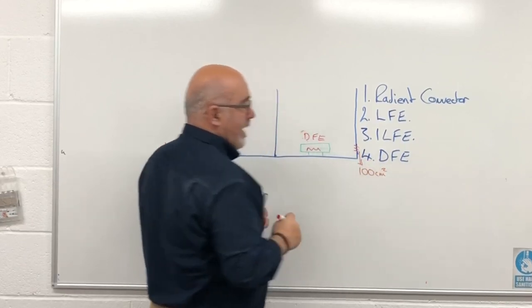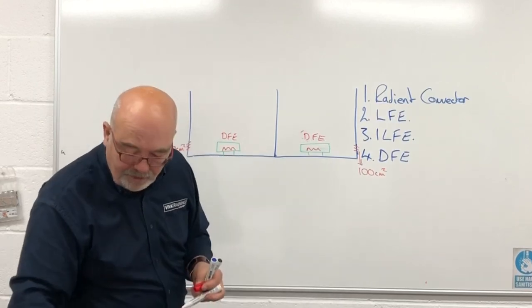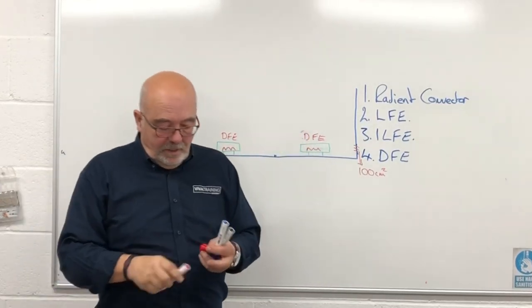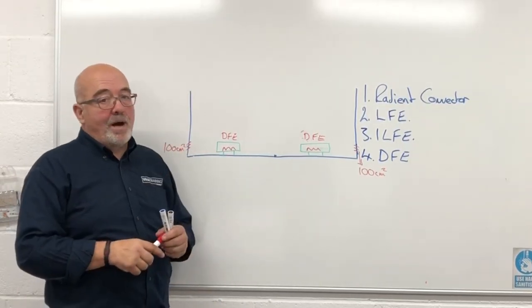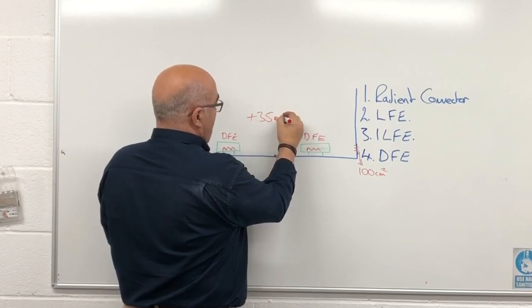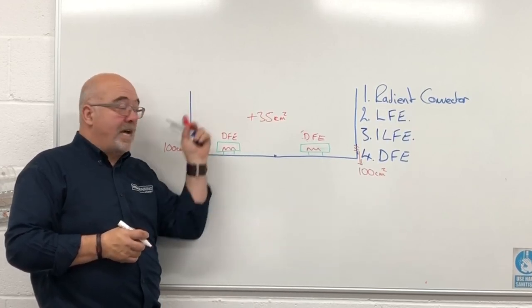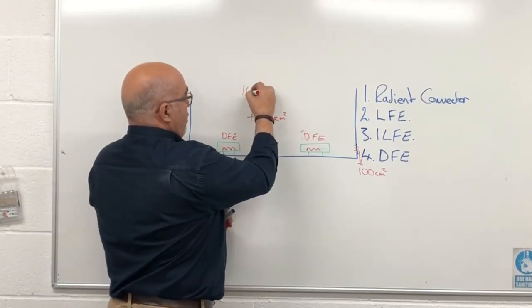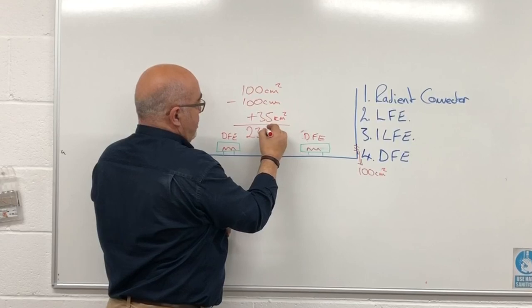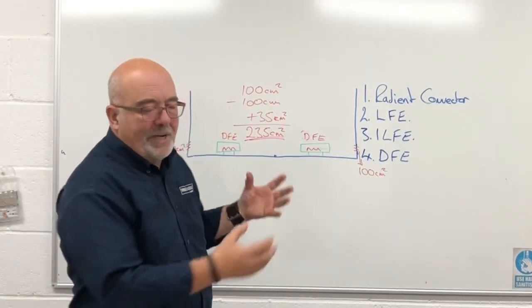If the manufacturer's instructions state no additional ventilation is required, then the 35 cm² of free air is sufficient. However, if you don't have the manufacturer's instructions, you must assume — even if it's under 7 kW — that a DFE needs 100 cm² of free area. If you then have two DFE fires in one room with the wall removed, you'd need 100 + 100 + 35 = 235 cm² of free area. Even though a gas fire is technically still an open flue appliance, the same ventilation requirement doesn't always follow.